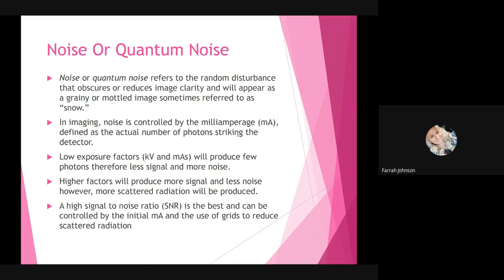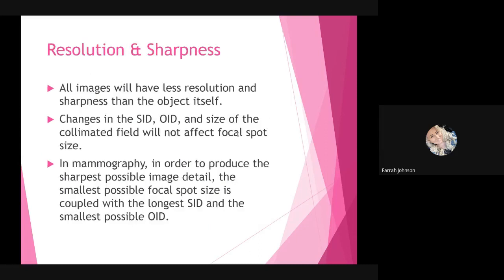However, more scattered radiation will be produced. And a high signal to noise ratio, or SNR, is the best and can be controlled by the initial mA and the use of grids to reduce scattered radiation. So that brings us to resolution and sharpness. So all images will have less resolution and sharpness than the object itself. Changes in your SID, your OID, and the size of your collimated field will not affect focal spot size.